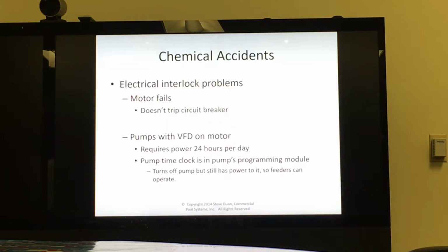Problem with electrically interlocking chemical feeders or chemical controller: sometimes when a motor fails, it will trip the circuit breaker. There are times when the motor fails and the circuit breaker doesn't trip. So you still have power coming down to the motor, but it isn't working. Which means you've got a branch line going to the chemical controller or the feeders, and it still has power, so it thinks it can feed, because the circuit breaker didn't trip. This is particularly a problem when you have feeders electrically interlocked, no chemical controller, because there's no flow switch to control them. So that's a big problem.